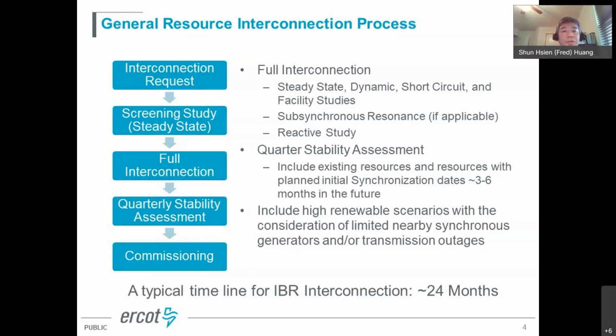If generators are proposed close to series capacitors, those projects need to perform a subsynchronous resonance analysis, and most of the time those studies require detailed SSR analysis. We also require all projects to demonstrate sufficient voltage support capability in the interconnection process, so they can provide adequate voltage support when connecting to the ERCOT system.